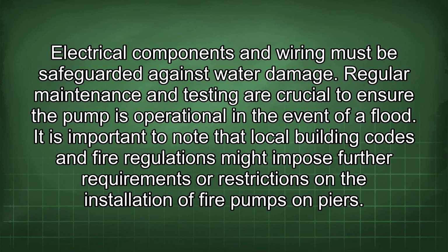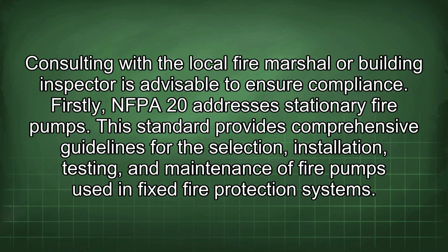Electrical components and wiring must be safeguarded against water damage. Regular maintenance and testing are crucial to ensure the pump is operational in the event of a flood. It is important to note that local building codes and fire regulations might impose further requirements or restrictions on the installation of fire pumps on piers. Consulting with a local fire marshal or building inspector is advisable to ensure compliance.